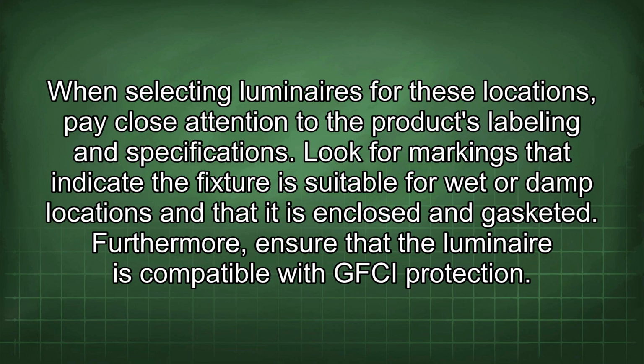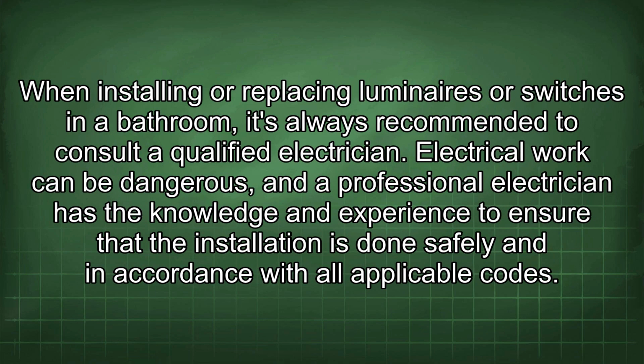When selecting luminaires for these locations, pay close attention to the product's labeling and specifications. Look for markings that indicate the fixture is suitable for wet or damp locations and that it is enclosed and gasketed. Furthermore, ensure that the luminaire is compatible with GFCI protection. When installing or replacing luminaires or switches in a bathroom, it's always recommended to consult a qualified electrician. Electrical work can be dangerous, and a professional electrician has the knowledge and experience to ensure that the installation is done safely and in accordance with all applicable codes.